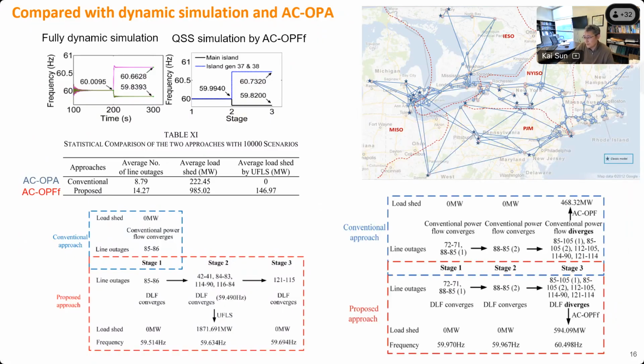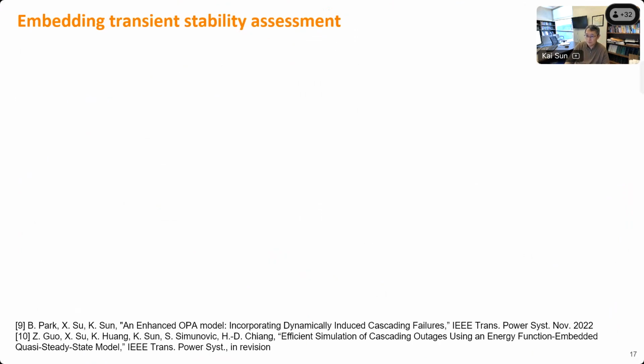Here's another comparison, between the frequency-independent model and the frequency-dependent model. They can give you very different results. If you only run power flow to simulate cascading failure, that's not accurate, because any power flow solver will assume 60 Hertz from the first event until the end of the simulation. But under cascading failure, the frequency can change largely. So you need to integrate the frequency deviation into your simulation, even if you don't want to run a time domain simulation.